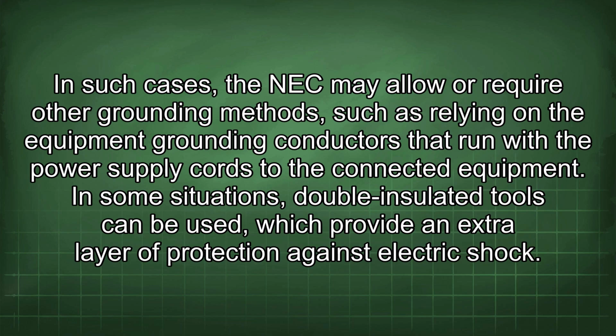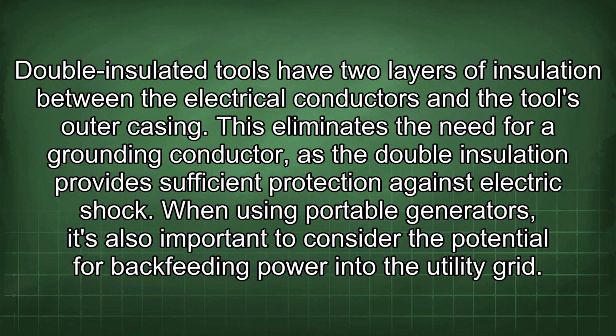In some situations, double insulated tools can be used, which provide an extra layer of protection against electric shock. Double insulated tools have 2 layers of insulation between the electrical conductors and the tool's outer casing. This eliminates the need for a grounding conductor, as the double insulation provides sufficient protection against electric shock.